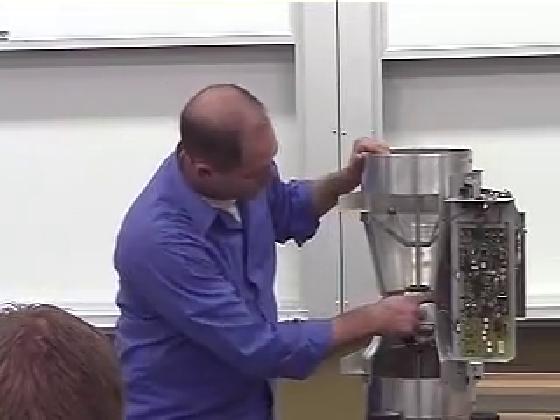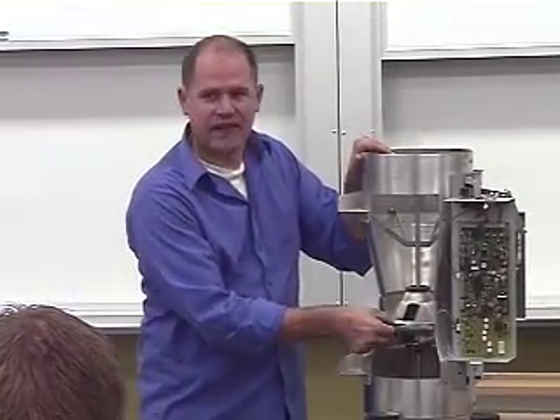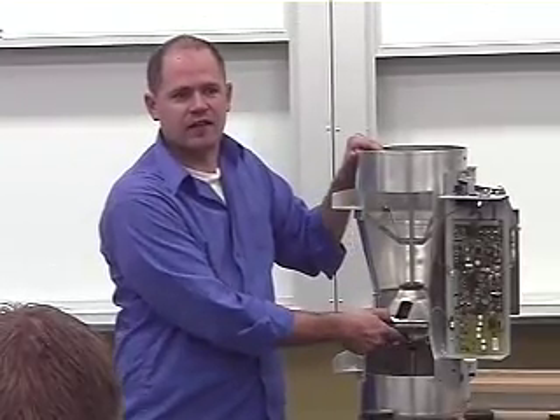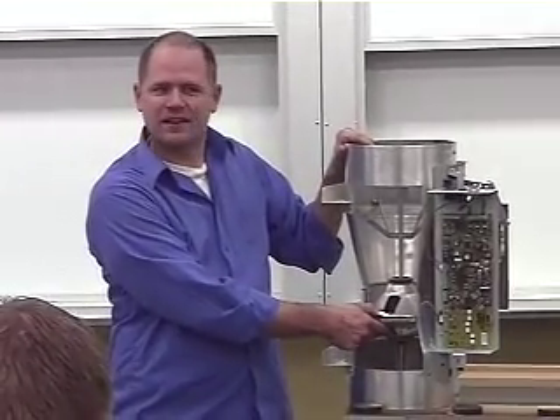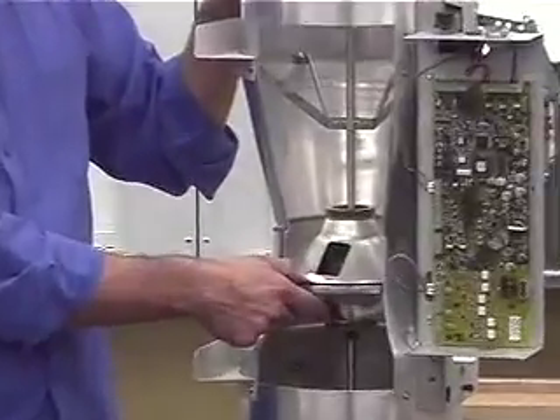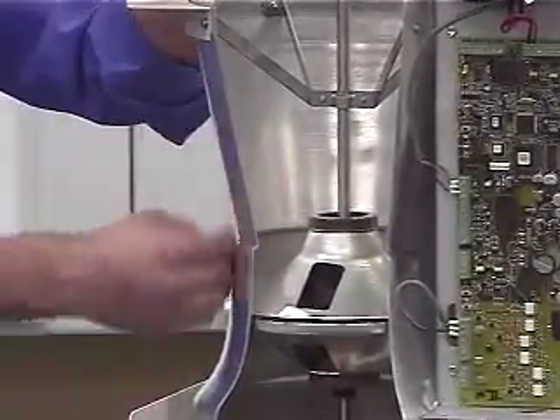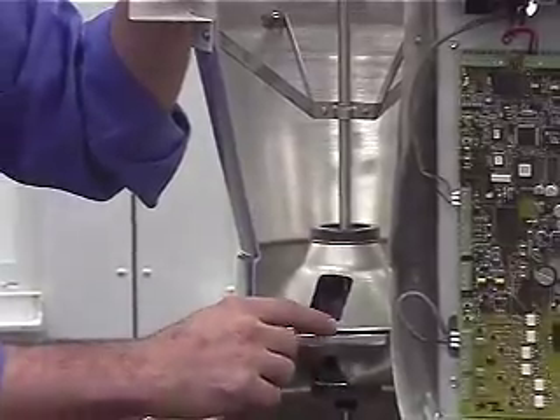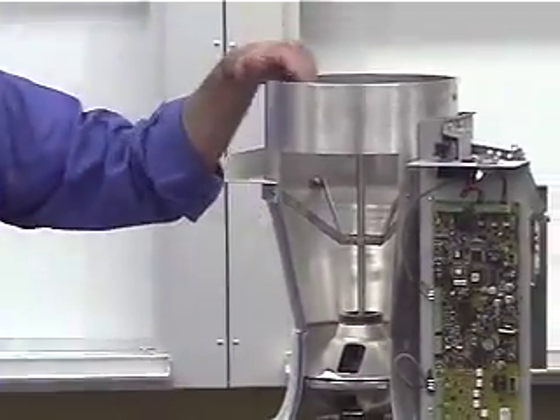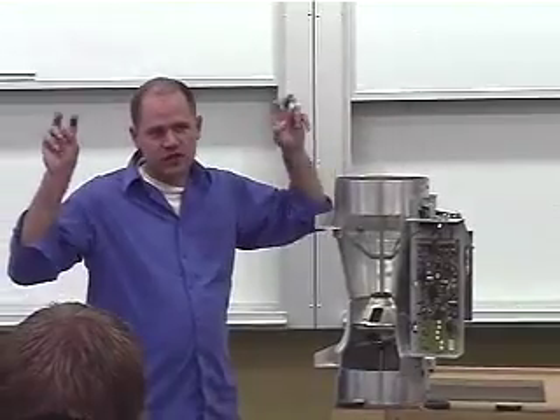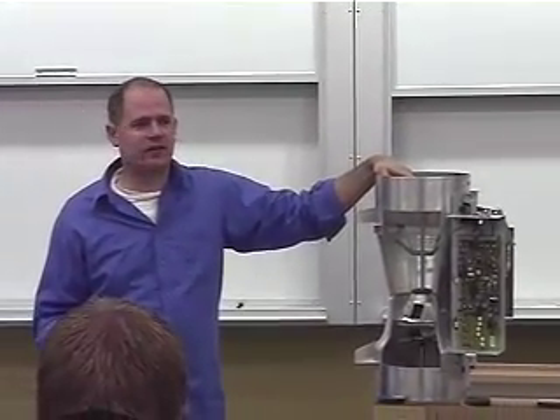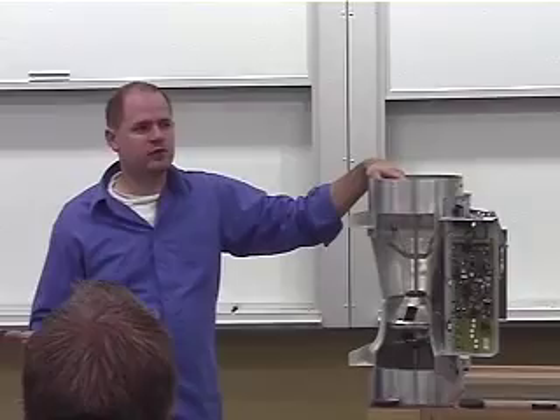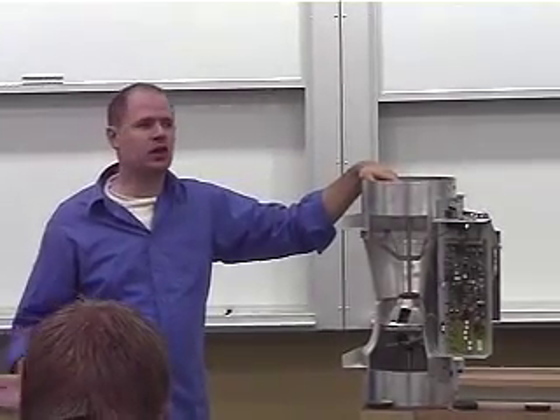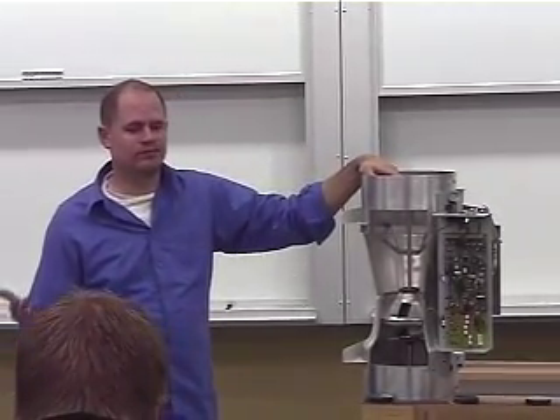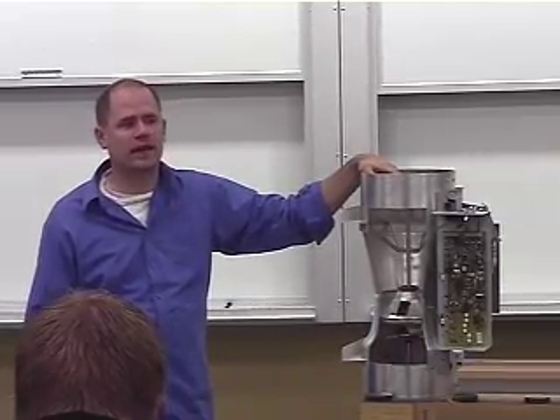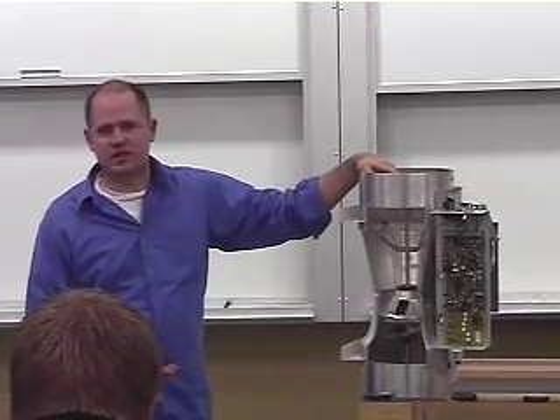This specific model has a ridge inside of it and a gasket on here. This is a shutoff valve. I don't know for sure if you guys have any on here. I don't think so. I didn't see any on the sheets. Most of yours will be smoother here, and there will be no gasket on this. And basically that means there's a minimum flow that when the valve is completely closed, you're still getting some flow through the valve. Typically you have your minimum flows anyway, so you don't need zero flow through a valve unless you have a vivarium area that needs shut off for cleaning or stuff like that. In this case, you have just standard lab flows.